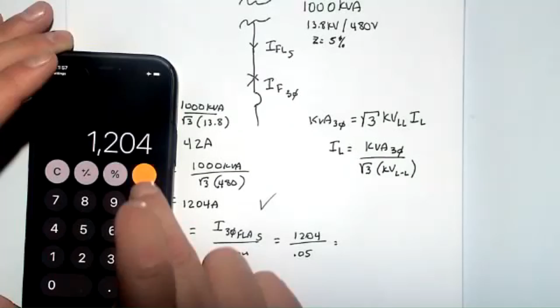That's our fault current. Since the impedance is 5%, or 0.05, this number is 20 times the full load amps. Again, interesting things to think about. When you think about the impedance, 1 over 0.05 is a ratio of 1 to 20, so the ratio of the fault current to the full load amps is 20 times. And that's how we're going to size our kA rating for our breakers. So those are just a few of the things that we want to think about.